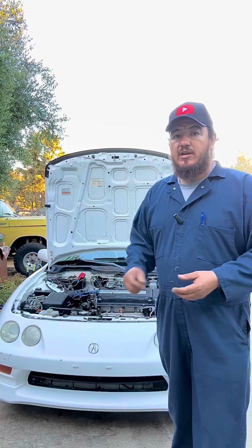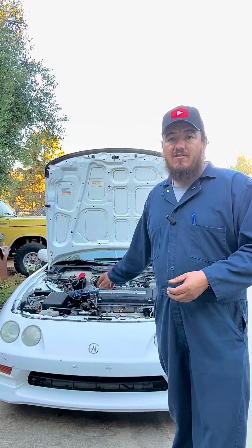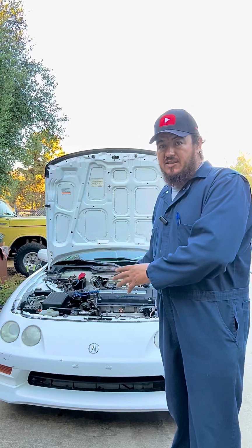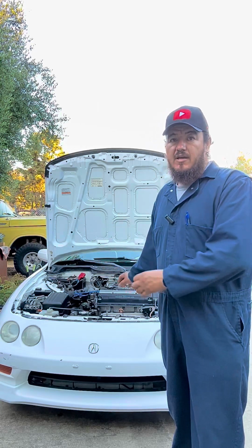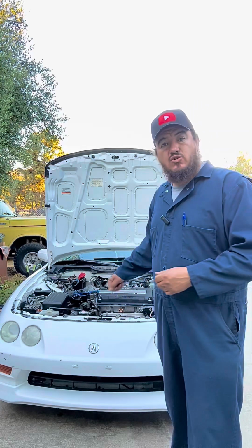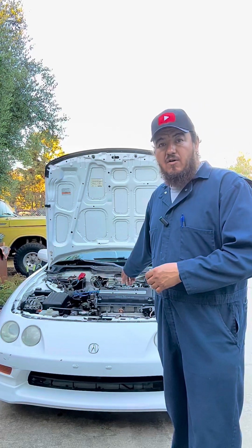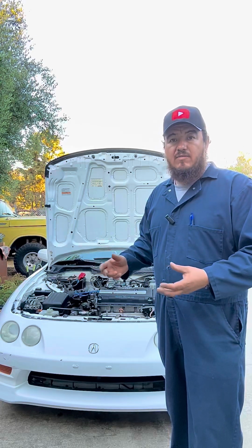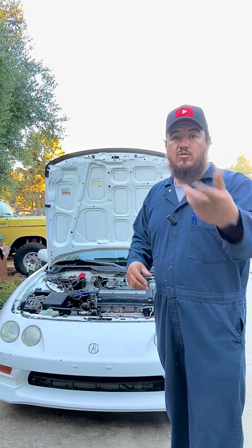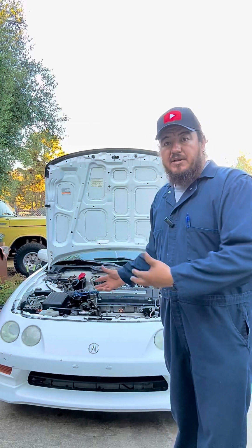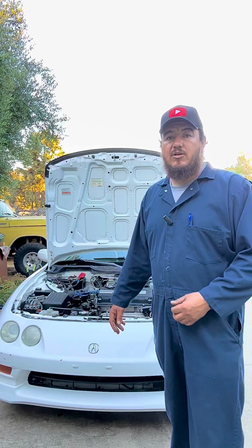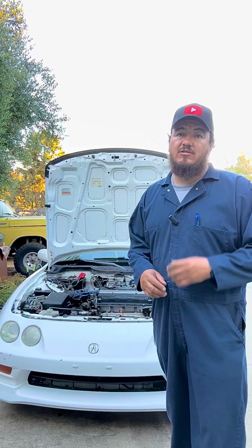Once we get to that point, we're going to show you the replacement of the valve, and then we have to recharge the system. But for now, this is just the diagnosis where we were losing the freon because we kept adding and adding, and now we know where the problem is. Now we just use compressed air to blow on that orifice, get the water out of it, evaporate it, and then put the caps back on. Then we can continue with the next step, which is recovering the freon to work on the replacement. We'll have the video on how we do the replacement of those valves in the future.